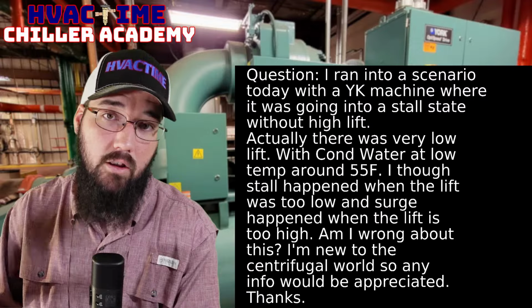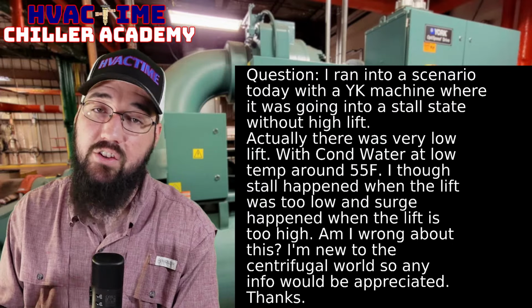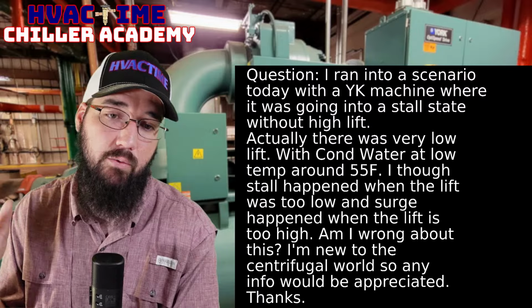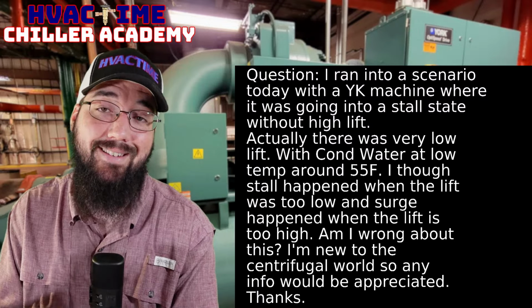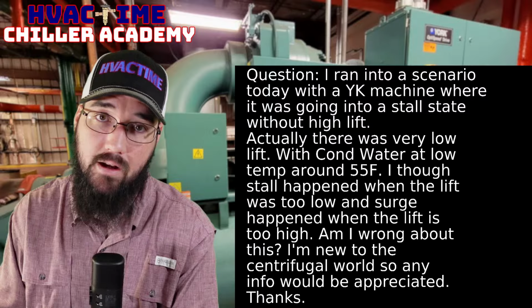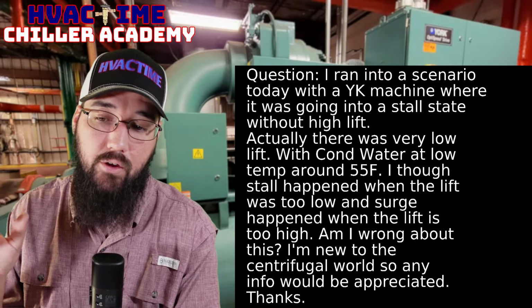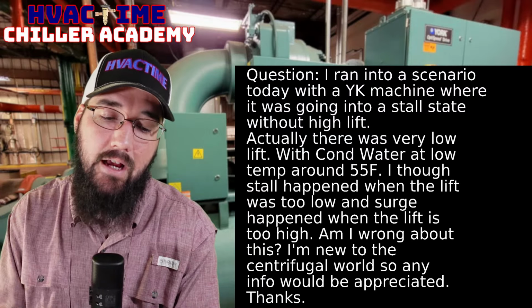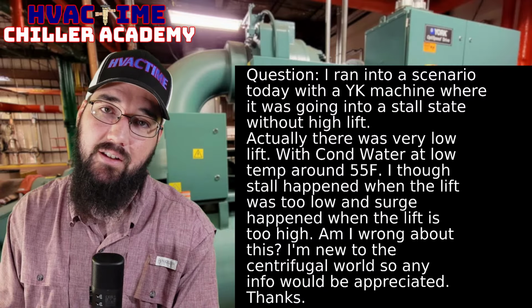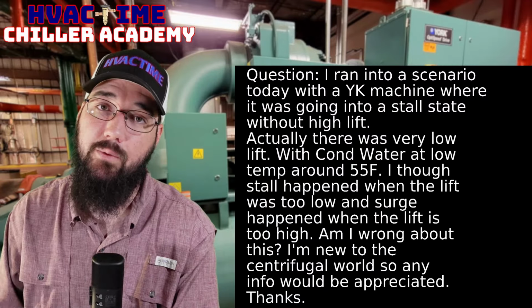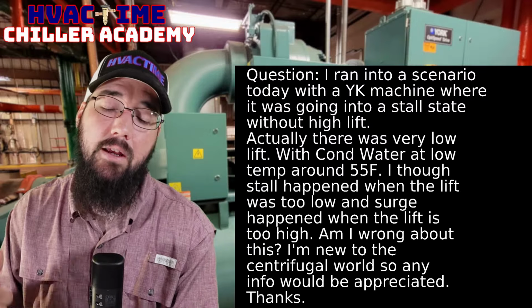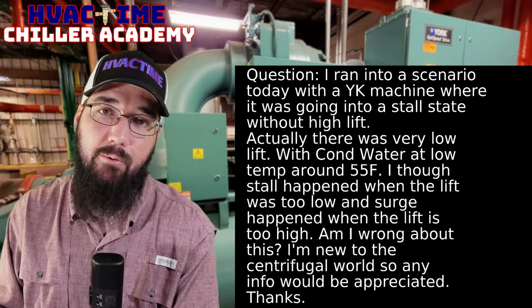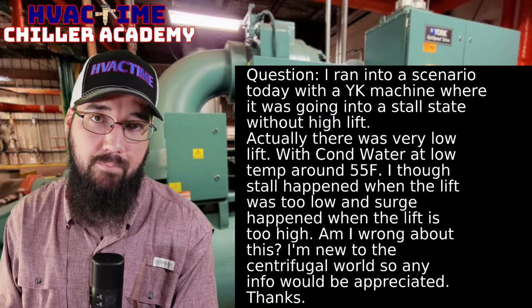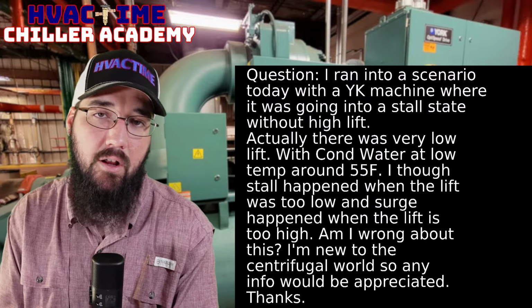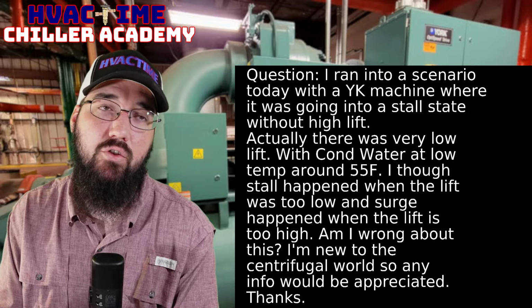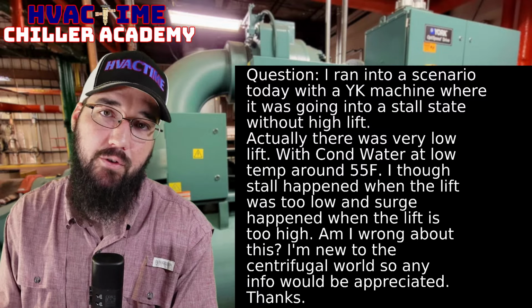And there are a lot of other machines that will do 55 all day, especially these mag bearings. These mag bearings will fly down in there, but these mag bearings have the same limitations. Just bear that in mind. We can get down there and stay there more consistently with a mag bearing and have fewer issues because we don't have to worry about migration. But we still have to stay within our surge and choke boundaries. And those mag bearings are not excluded from those boundary zones on that compressor.